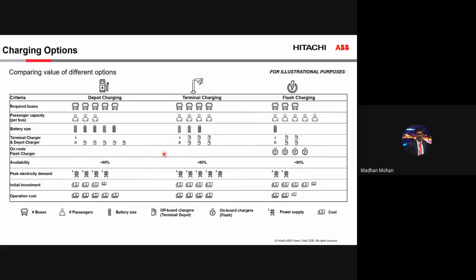Yes, true. But to take care of that, you might have seen in the flash charger, I have shown one energy storage unit. So it is not a direct charging from the charger to the pole. We keep on charging the battery or energy storage unit through the rectifier, and the energy is transferred only from battery to battery, so that we are avoiding any peak demand to the grid. So the grid will have a constant load to only charge the battery that is put at the station. Whenever the bus comes, only the energy available in the battery is transferred to the battery in the bus via the charging port. In that way also we are avoiding the peak demand to the grid. This is about the power demand.